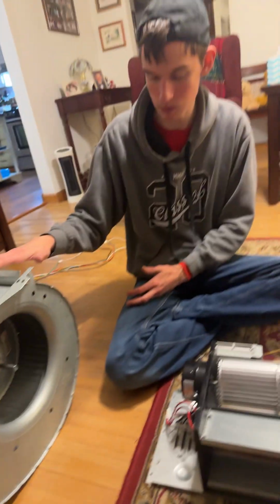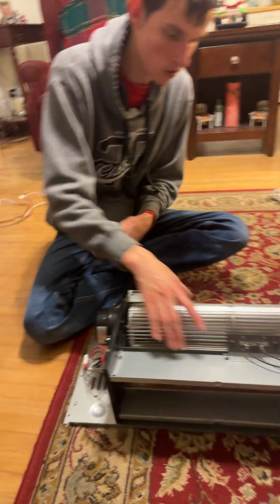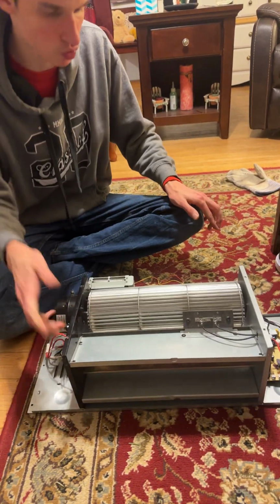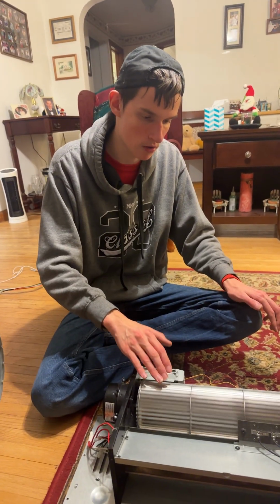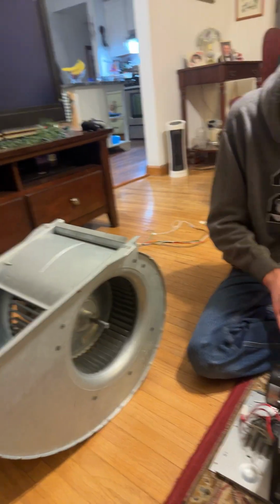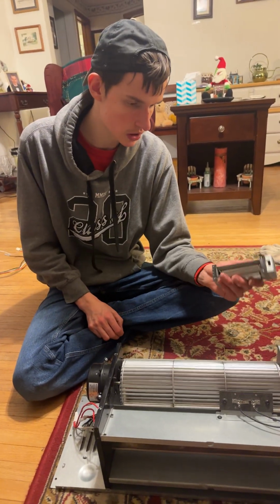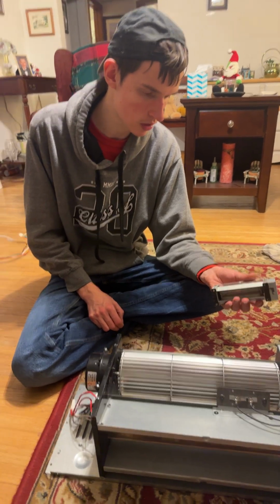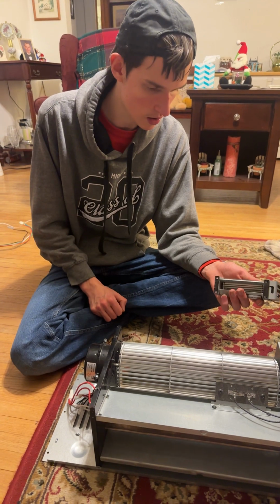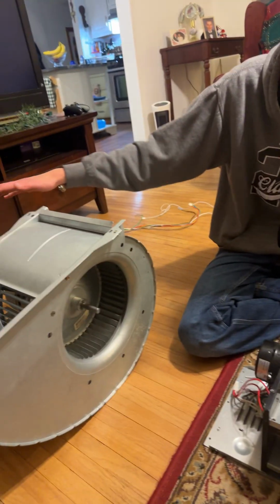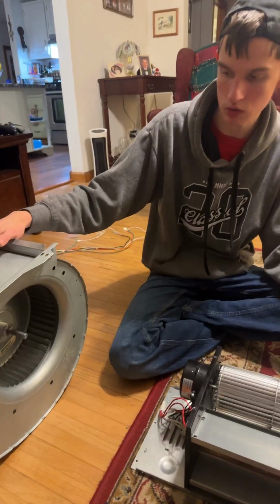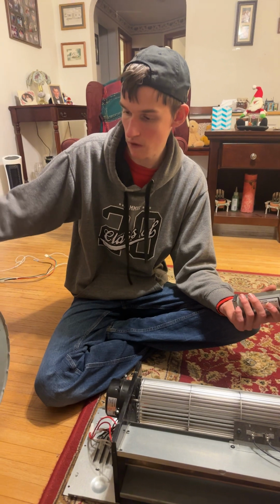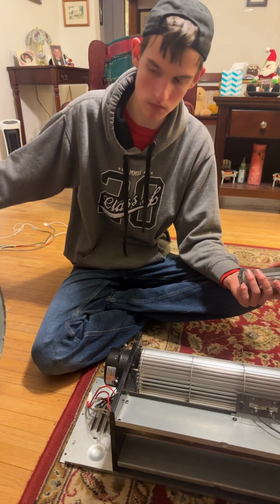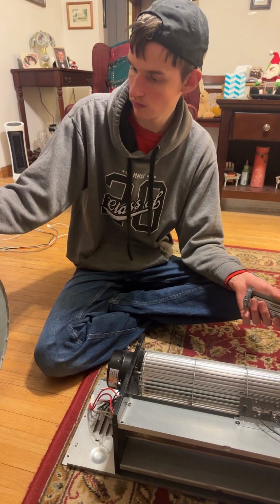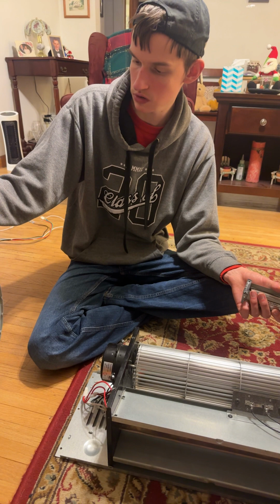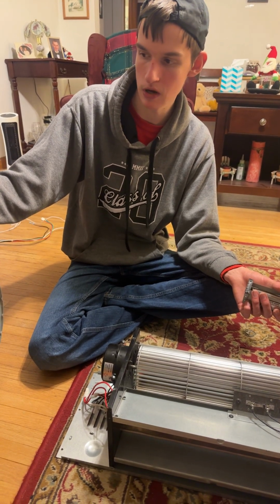You need that high RPM and static pressure on these blowers. On a heater blower like this, it only spins up to about 2100 RPM. It doesn't need as much static pressure as a furnace blower. This one would probably spin up to about 1600 RPM, it doesn't need to spin as fast. A traditional blower like this, or an old gas one, if you combined two blowers into one unit, it'd probably put out 2,000 CFM, cubic feet per minute.